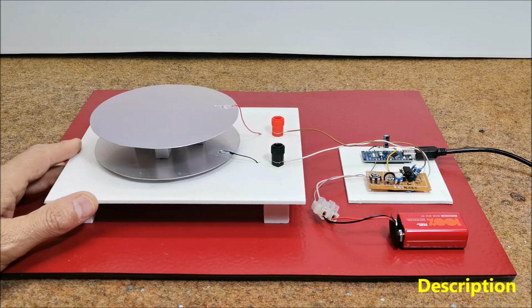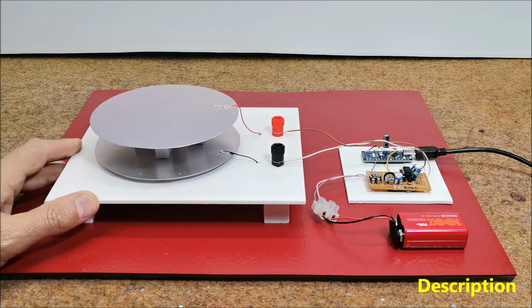Generally, this type of instrument is divided into contact-based meters, which measure charge by direct contact with the surface, and non-contact field meters that use electrostatic induction to measure charge from a distance. Another division is based on the duration of the measurement, namely momentary checks in different locations and continuous 24/7 monitoring systems.